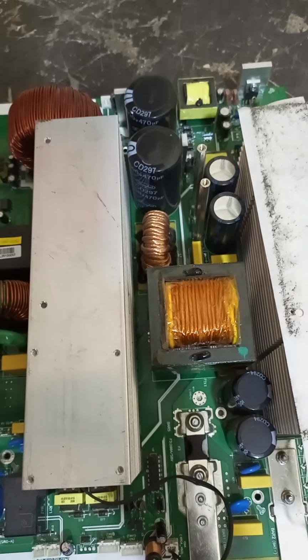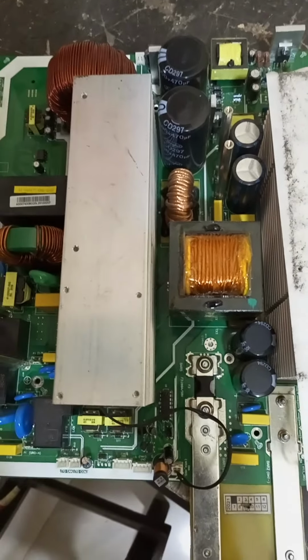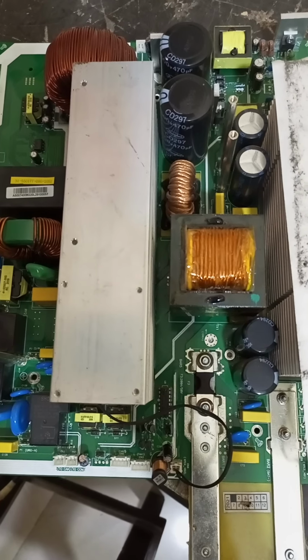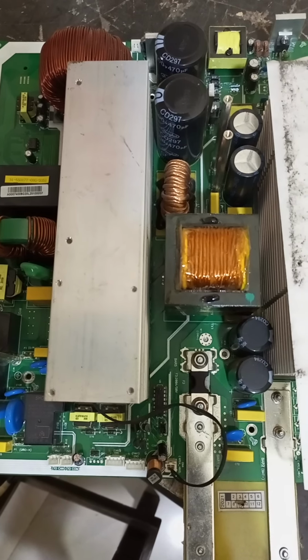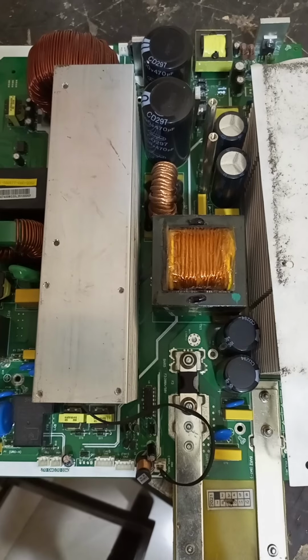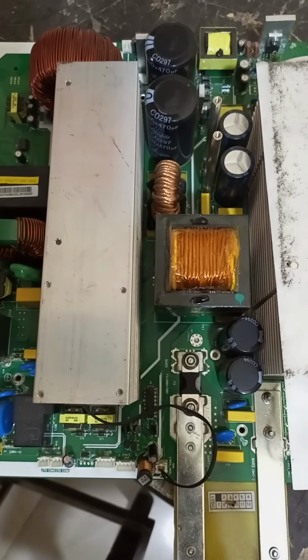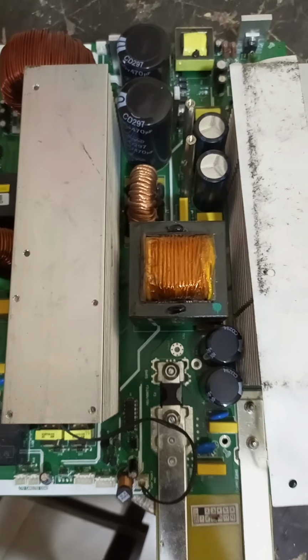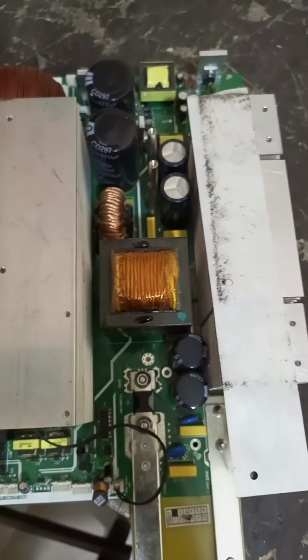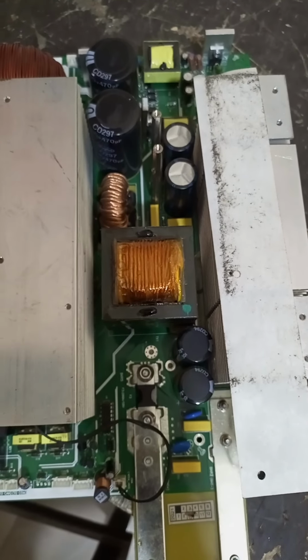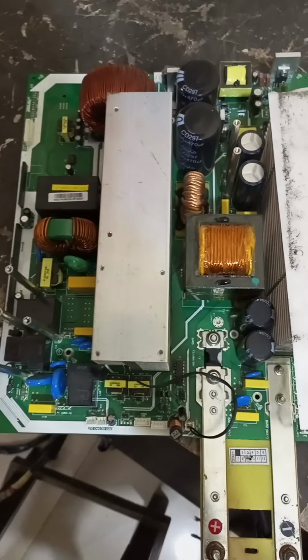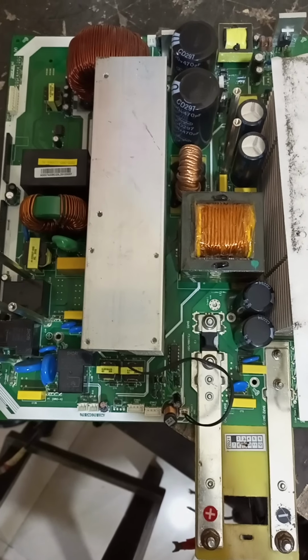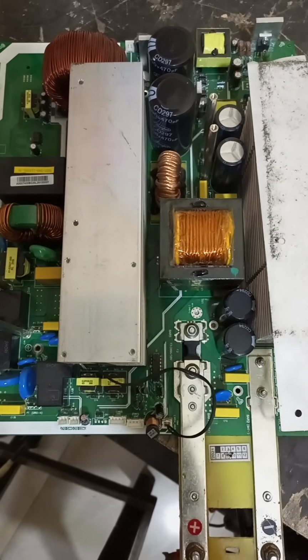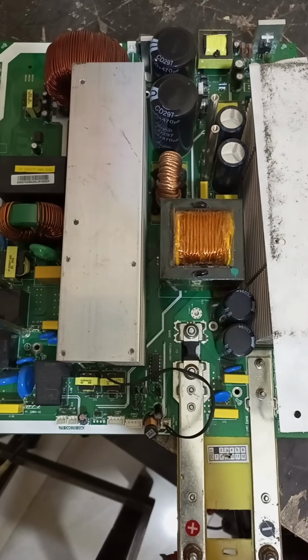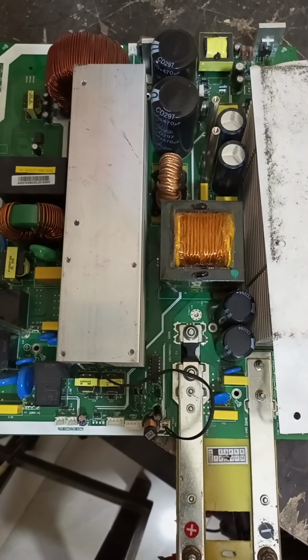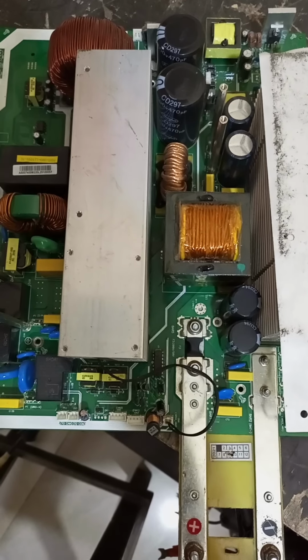You have a 5 kVA MKS that doesn't come up. Normal 5 kVA that doesn't come up. It's not just restricted to 5 kVA, any hybrid system that looks like this kind of panel, you turn it on and nothing happens, no lights, no display, no nothing.